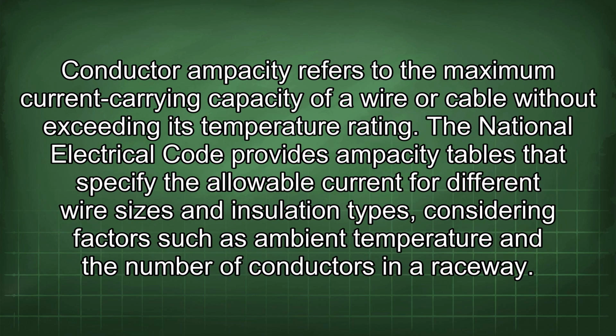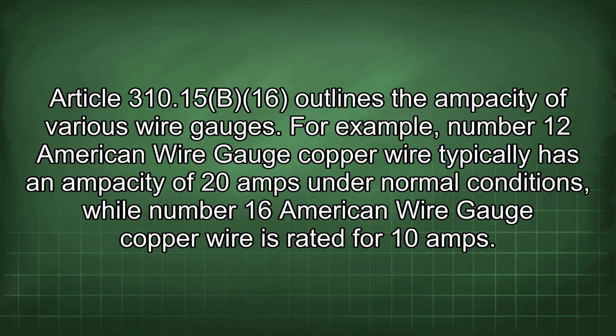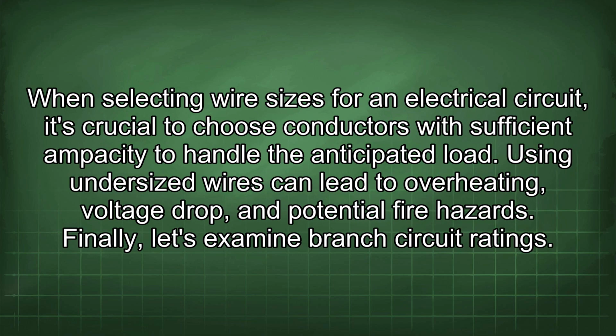Next, let's consider conductor ampacity. Conductor ampacity refers to the maximum current carrying capacity of a wire or cable without exceeding its temperature rating. The National Electrical Code provides ampacity tables that specify the allowable current for different wire sizes and insulation types, considering factors such as ambient temperature and the number of conductors in a raceway. Article 310.15(B)(16) outlines the ampacity of various wire gauges. For example, number 12 American wire gauge copper wire typically has an ampacity of 20 amps under normal conditions, while number 16 copper wire is rated for 10 amps. When selecting wire sizes for an electrical circuit, it's crucial to choose conductors with sufficient ampacity to handle the anticipated load. Using undersized wires can lead to overheating, voltage drop, and potential fire hazards.